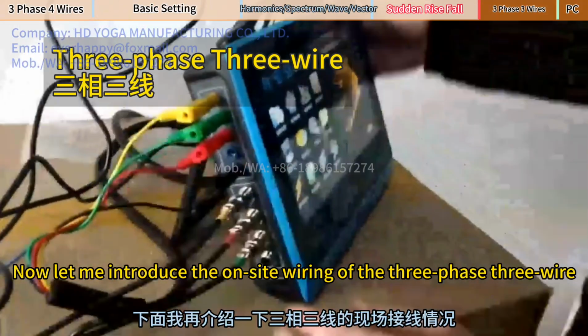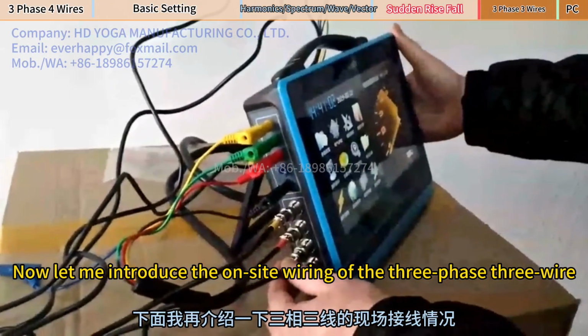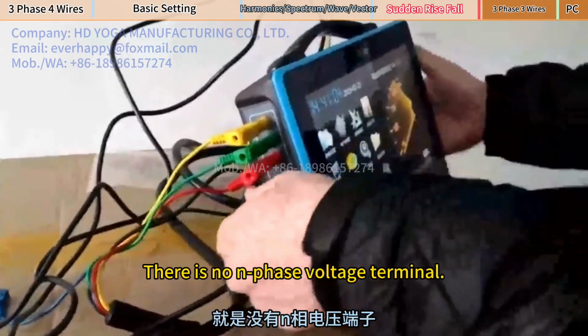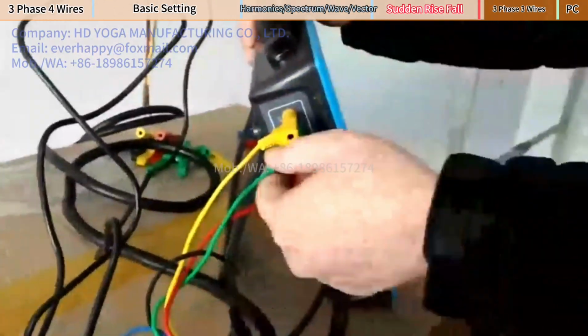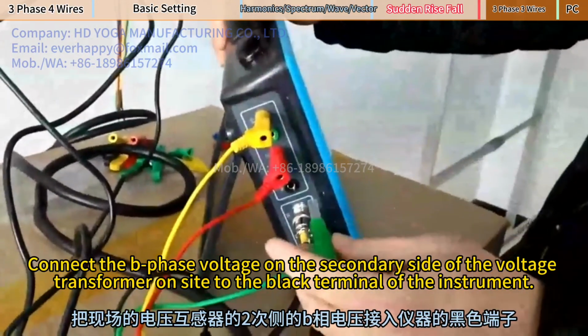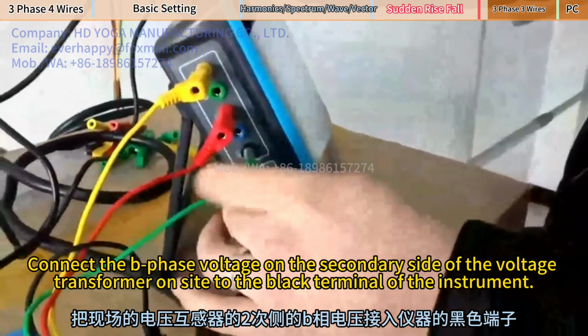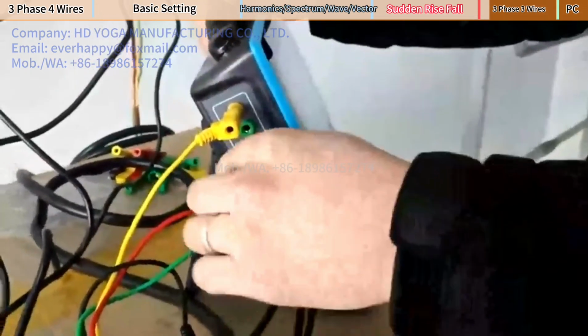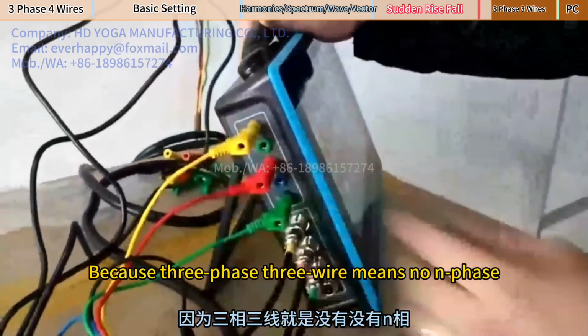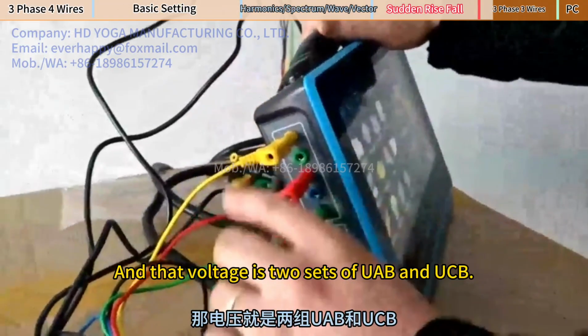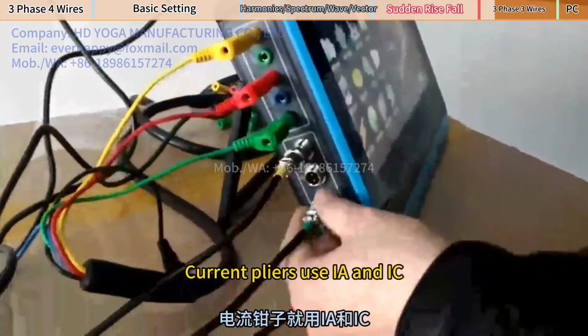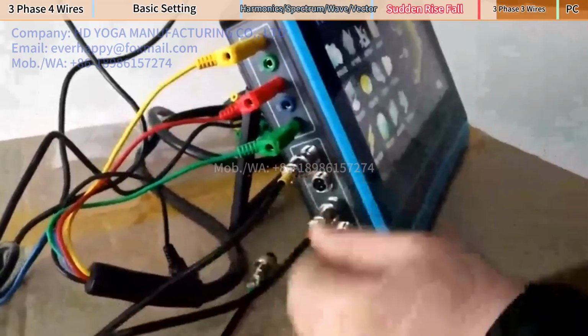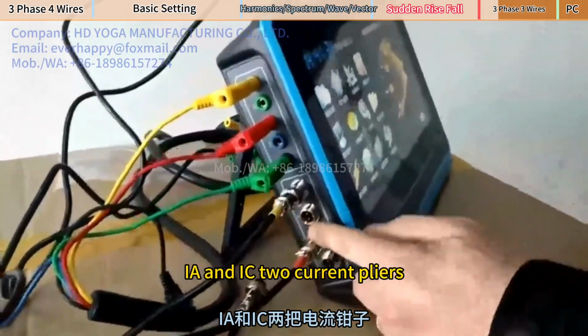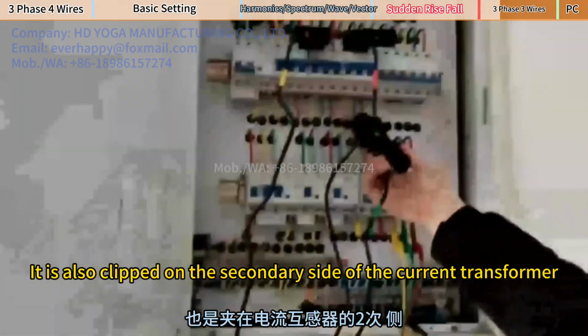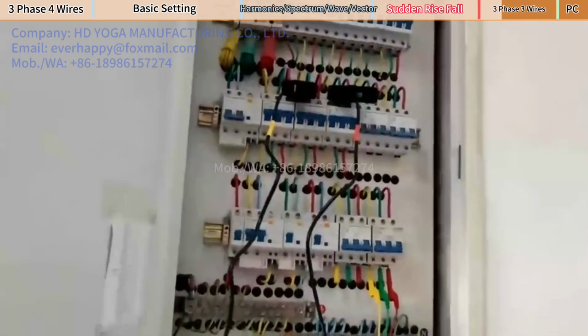Now let me introduce the on-site wiring of the 3-phase 3 wire. When 3-phase 3 wire, there is no N-phase voltage terminal. Connect the B-phase voltage on the secondary side of the voltage transformer on site to the black terminal of the instrument, because 3-phase 3 wire means no N-phase. And that voltage is 2 sets of UAB and UCB. Current pliers use IA and IC. IA and IC 2 current pliers. It is also clipped on the secondary side of the current transformer. The same principle. The operation process is the same.